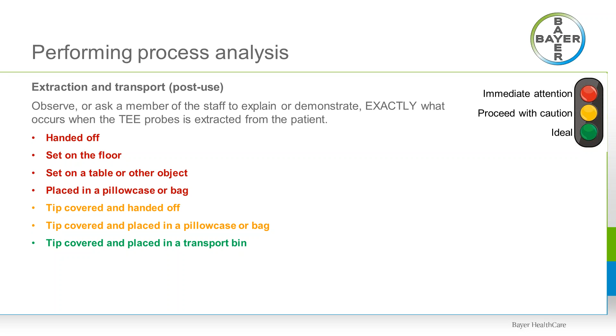Is the probe merely handed off to someone? Is it set on the floor or on top of another device or table? Is it placed in a pillowcase or a biohazard bag? Is the probe placed in a bin? And again, is tip protection installed? Ideally, the probe is placed within a storage bin with some type of tip protection. The probe should never just be handed off or set on the floor or a table or on top of another device. You're really asking for trauma to occur if one of those methods is employed, especially if tip protection is not used.